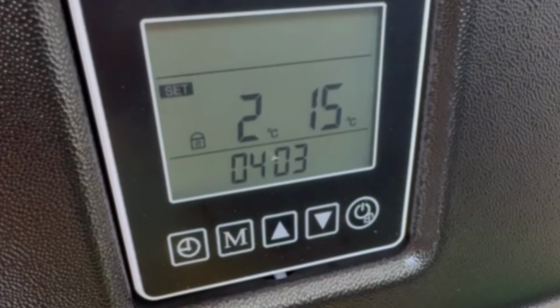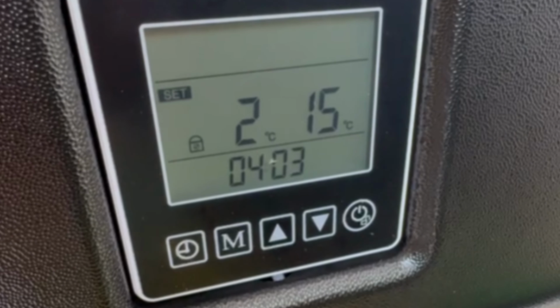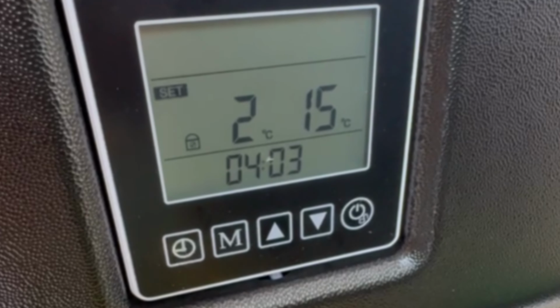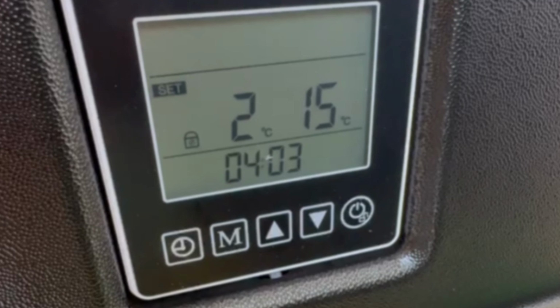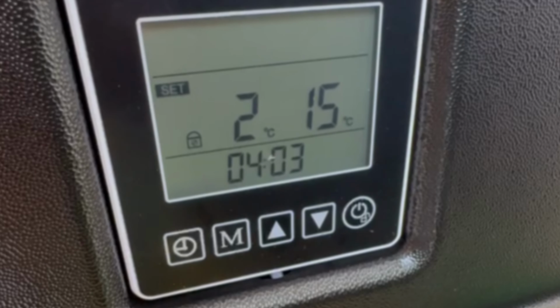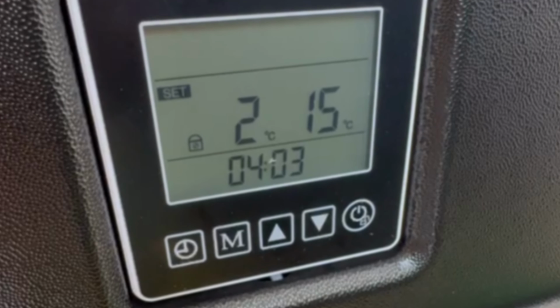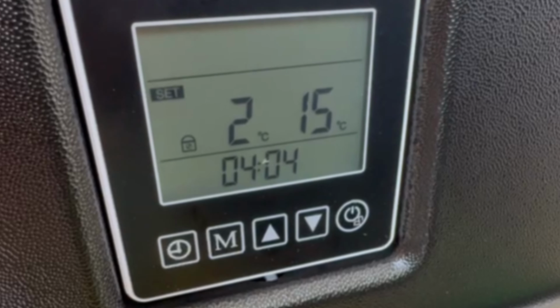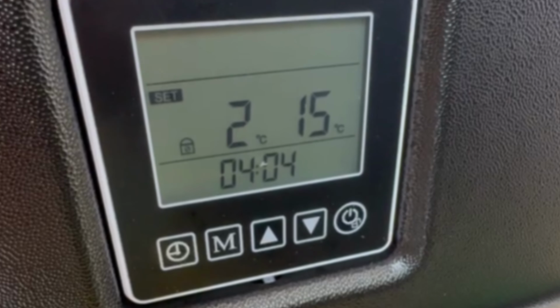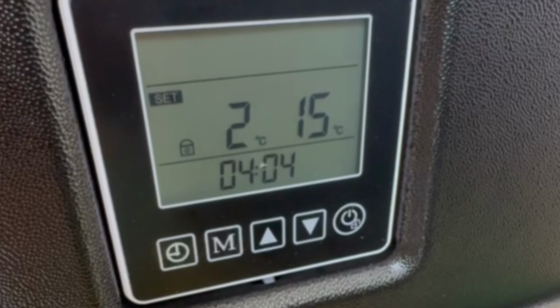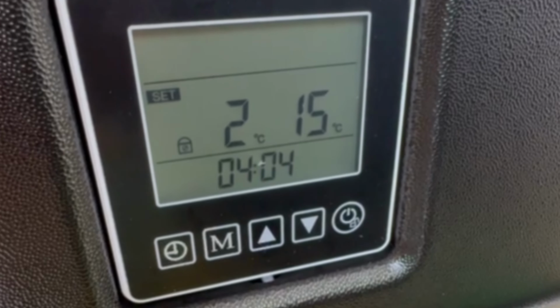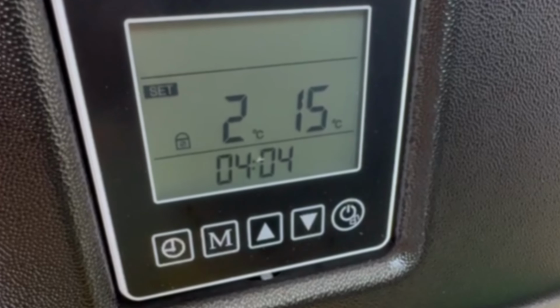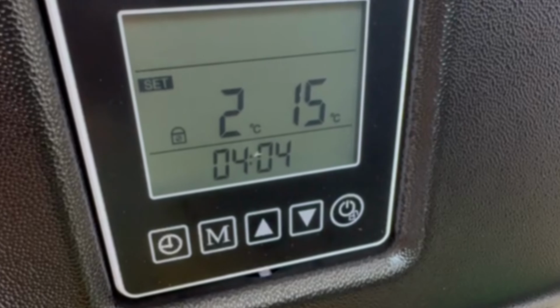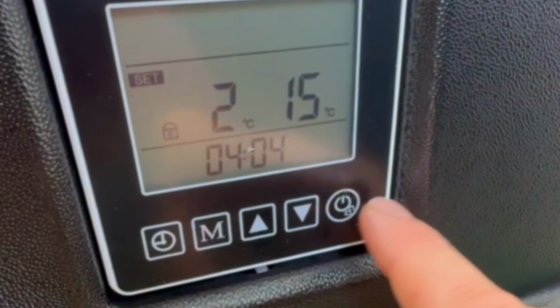The other logic is that the fan goes off, so the chiller is no longer trying to achieve temperature, the fan goes off, but the pump stays on. This is the way you would set it if you're going to wire the UV into the chiller, because you want the chiller to stay on even when the fan isn't operating on the chiller. So here's how to do it.